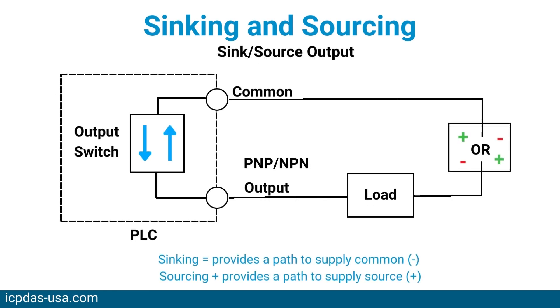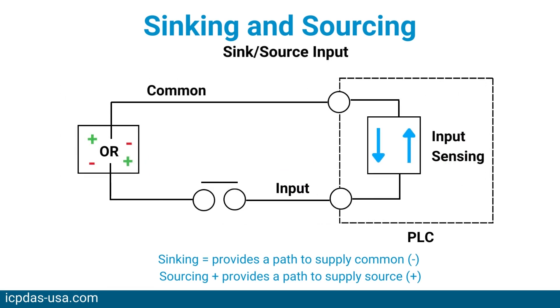Sink-source I/O circuits combine sinking and sourcing capabilities. The I/O circuit in the PLC will allow current to flow in either direction. The common terminal connects one polarity, and the I/O point connects to the other polarity through the field device, providing flexibility in making connections to the field power supply.